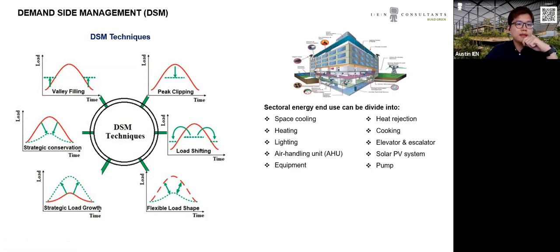In order to implement demand side management, a building's load profile needs to be known. Hence, submeters should be installed for all sectoral energy end use, which can be divided into space cooling, heating, lighting, AHU (air handling unit), equipment, heat rejection, cooking, elevator and escalator, solar PV system, and pumps and other systems you would like to monitor.